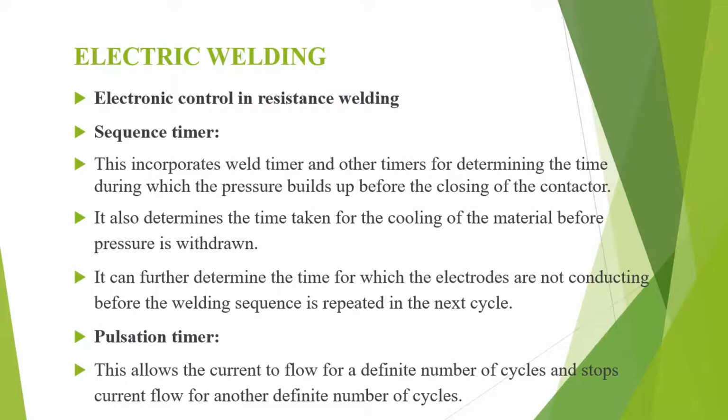It also determines the time taken for the cooling of the material before the pressure is withdrawn. This is known as hold time. Also, it can further determine the time for which the electrodes are not conducting before the welding sequence is repeated in the next cycle. This is known as off time.